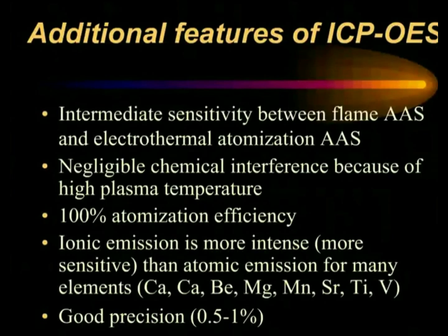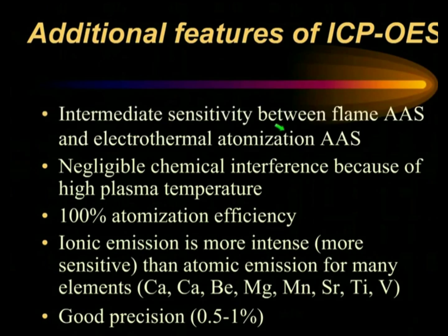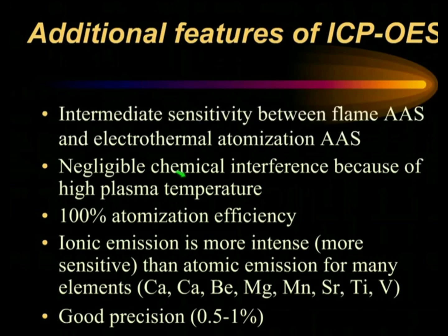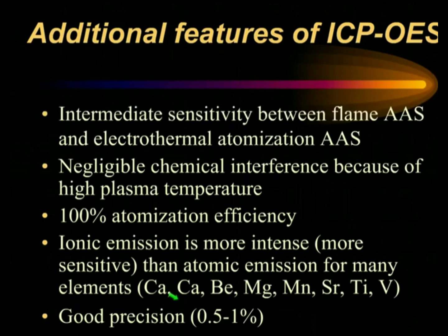The ICP as an emission source has a number of additional features. In terms of sensitivity, it is intermediate between what you get with a flame in atomic absorption spectroscopy and with a graphite furnace or electrothermal atomization in atomic absorption spectroscopy. It is very free of matrix effects, also called chemical interferences, because of the high plasma temperature — basically everything is completely atomized in the plasma. This is an advantage, but also a disadvantage if you want to do speciation analysis, because you have to separate the different species of a given element. Ionic emission is usually more intense and more sensitive than atomic emission for many elements, and measurements can be done with good precision, similar to flame atomic absorption.